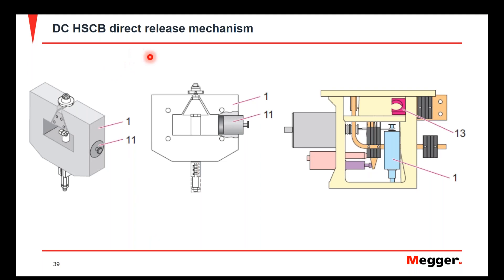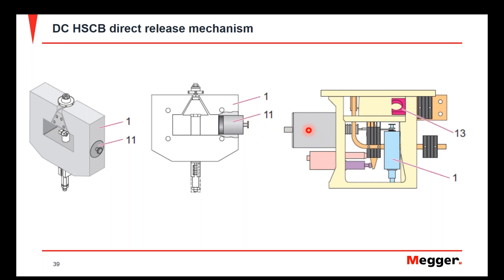The direct release mechanism is the component that helps operate the overcurrent or trip function for this style of breaker. It is an electromagnetic component, and the main current-carrying conductor goes through the middle of this device. When it senses an overcurrent condition, the magnet moves upward and hits a mechanical fork that forces the breaker open. This happens very quickly — as we saw on the curve — and even though the closing coil was holding the breaker shut, the trip mechanism overrides it and forces it open.